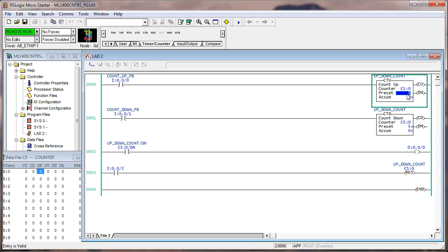Does this behavior vary from the timer data type when you change the preset after the done bit was set? Yes. With the timer data type, once it's done, it's done — you can mess with the preset and accumulate all you want, but when it's done it's done. Not so with the counter instruction. That's not how a counter data type and counter instructions work together. Other than the fact that timer data types count units of time and counter data types count events — that's where the similarity ends.